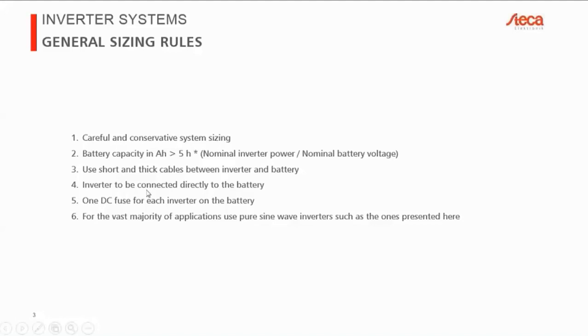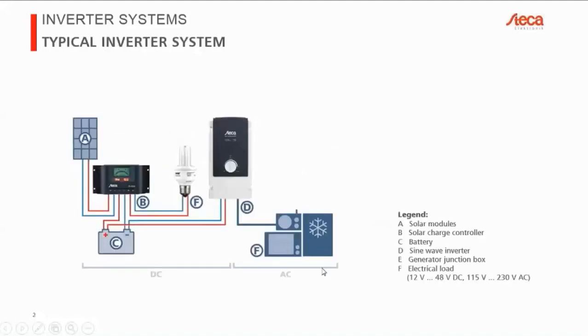The fourth rule is to always connect the inverter directly to the battery. I'll switch back to the previous typical inverter system. As I mentioned before, the inverter is connected to the battery. It is not connected to the DC output of the charge controller. Now, the reason is this.